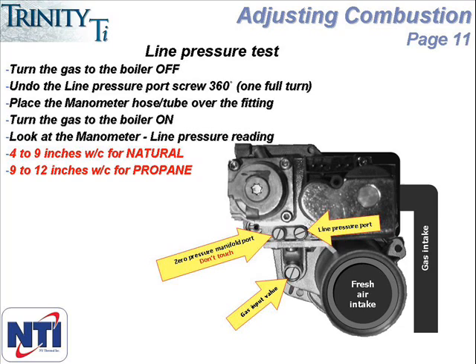or half PSI, can result in damage to the valve and could result in a leaking valve, which in turn could result in fire or explosion. So if you ever read a line pressure of 14 inches or above, disconnect the gas line and adjust the pressure at the regulator.